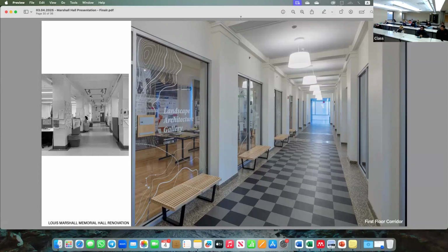So this floor is essentially cut in half right down the hallway, because there is no ductwork that goes from one side to the other. There's piping, there's conduits, but no ductwork cuts across this corridor because we did not have the room - the original plaster was so high to the ceiling that there was no way to get any ductwork across. So this was a fun exercise in how we turned ductwork up on end to get it through these soffits that you are on the other side of. Yeah, the soffits - those were very congested.